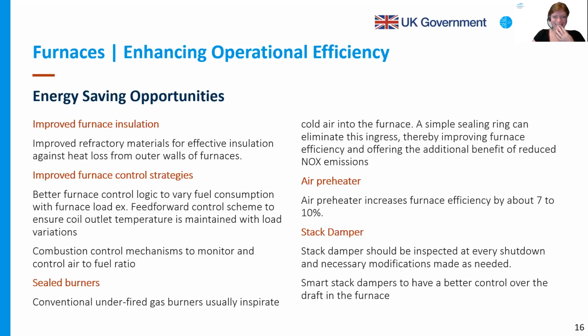Yeah. So another option is to also consider the stack damper. Stack damper is something that tends to be ignored. It should be frequently inspected at every shutdown, with necessary modifications made as needed. While many plants tend to have manually operated stack dampers, what tends to happen is that operators try to leave them fully open most of the time to prevent potential tripping of the heater. And this leads to ingress of cold air and also loss of hot flue gas. So there is a need to actually control the dampers, preferably with smart stack dampers, either with 2-blade or even 4-blade dampers nowadays. You have 4-blade dampers to have better control over the draft in the furnace. Sorry. Next slide.